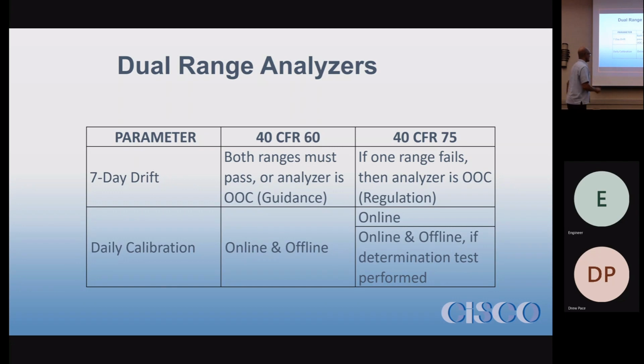On the other hand, Part 60 historically hasn't addressed the issue. And so we've gotten clarification from them, like I indicated in my presentation yesterday. Because EPA views the analyzer as having one detector for both ranges, if you go out of control for one range, they consider it out of control. So the guidance that the EPA has given us for 60 as well is the same as 75. If you fail on daily calibration, or on the 7-day drift test, on one of the ranges, both ranges are invalid.